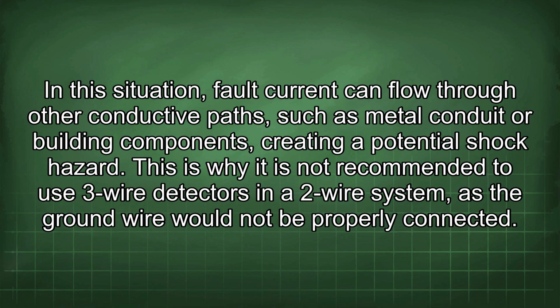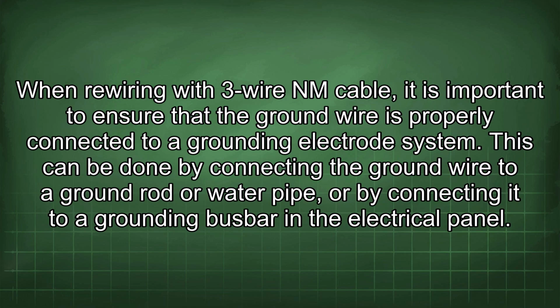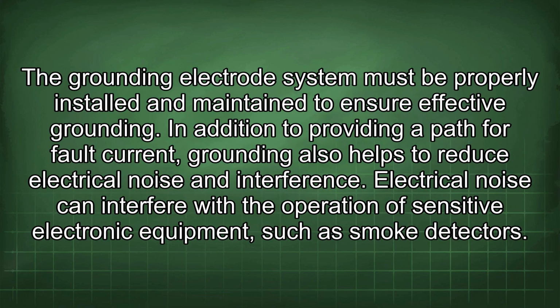This is why it is not recommended to use three-wire detectors in a two-wire system, as the ground wire would not be properly connected. When rewiring with three-wire NM cable, it is important to ensure that the ground wire is properly connected to a grounding electrode system. This can be done by connecting the ground wire to a ground rod or water pipe, or by connecting it to a grounding busbar in the electrical panel. The grounding electrode system must be properly installed and maintained to ensure effective grounding.